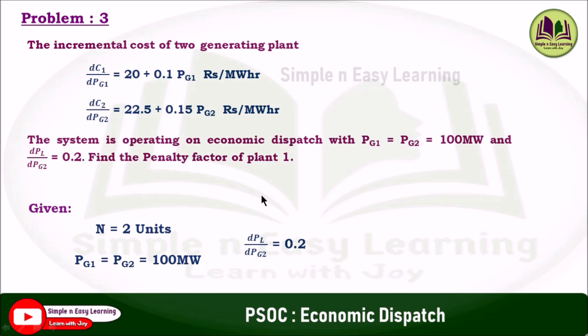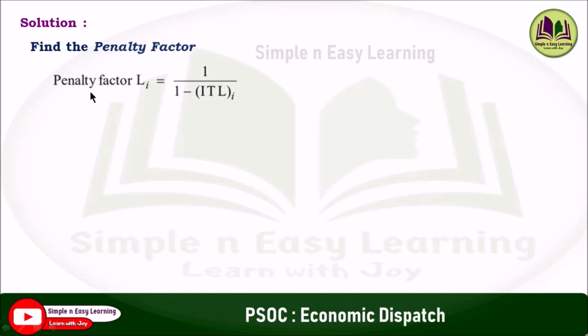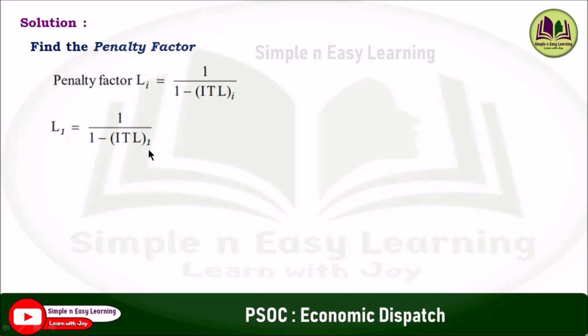In some problems, the cost function is given instead of the incremental cost. In such cases, we need to differentiate the cost function to get the incremental cost. For the solution, the penalty factor Li = 1 / (1 − ITL_i), where ITL is the incremental transmission loss. So L1 = 1 / (1 − ITL_1) and L2 = 1 / (1 − ITL_2).